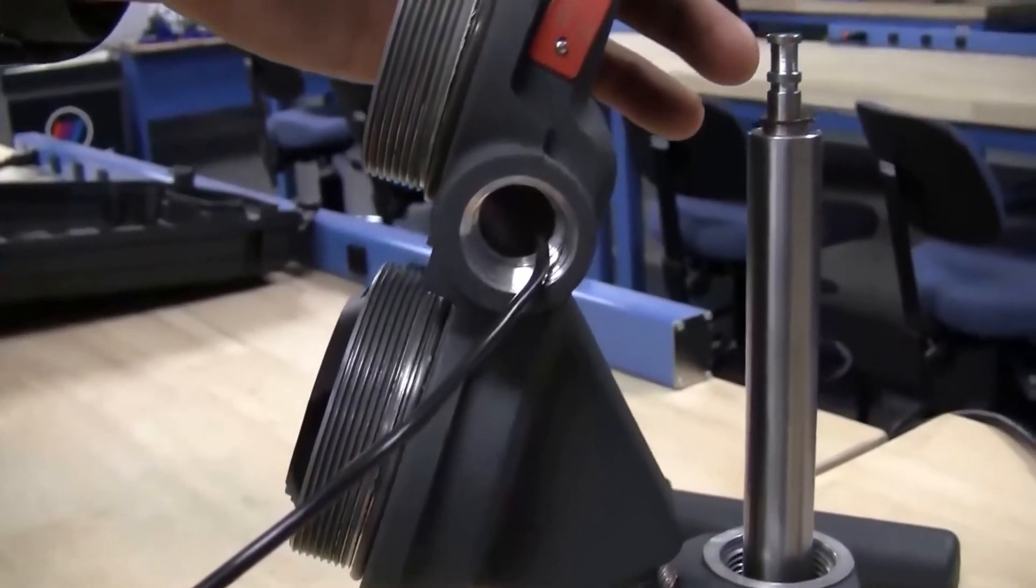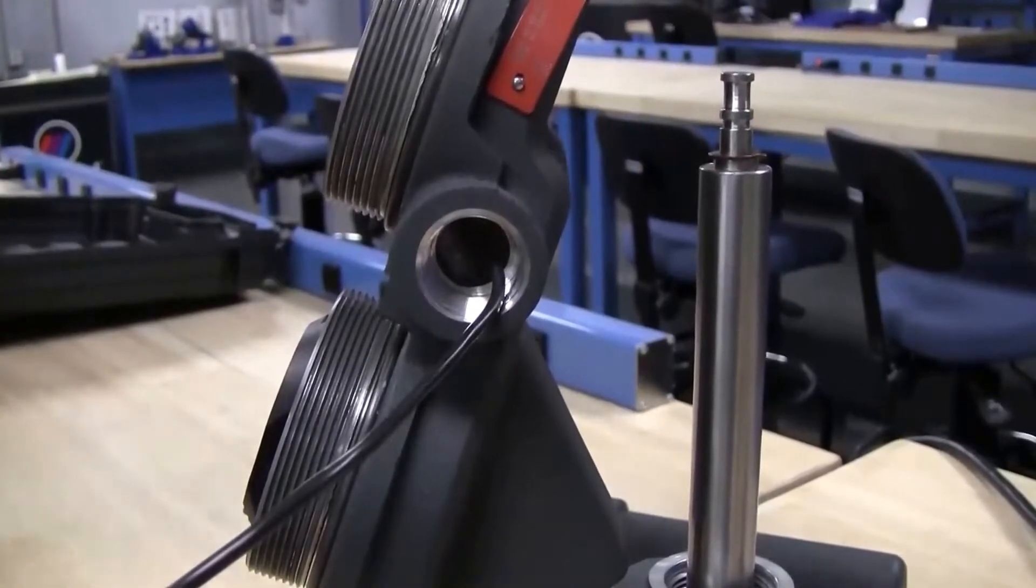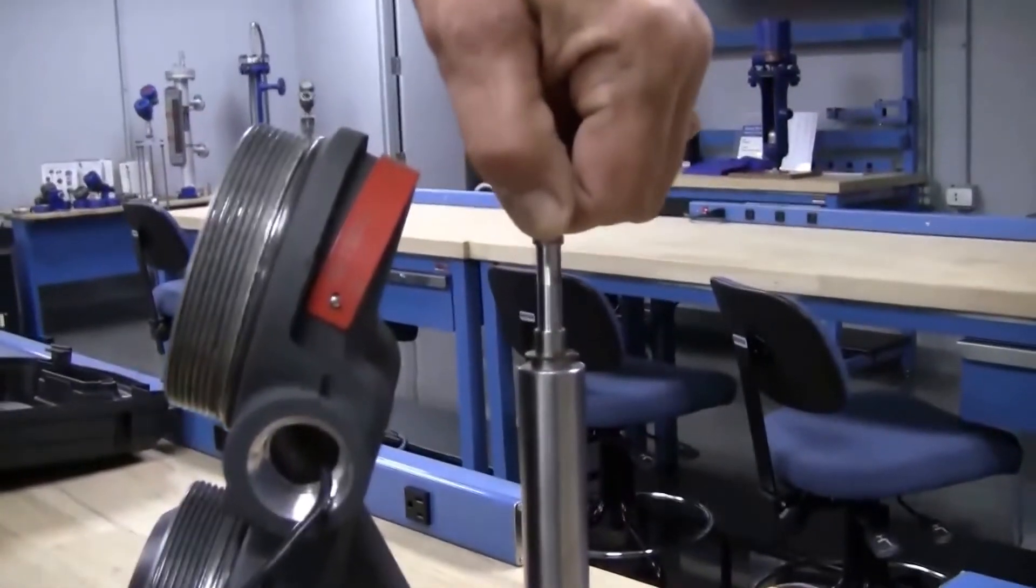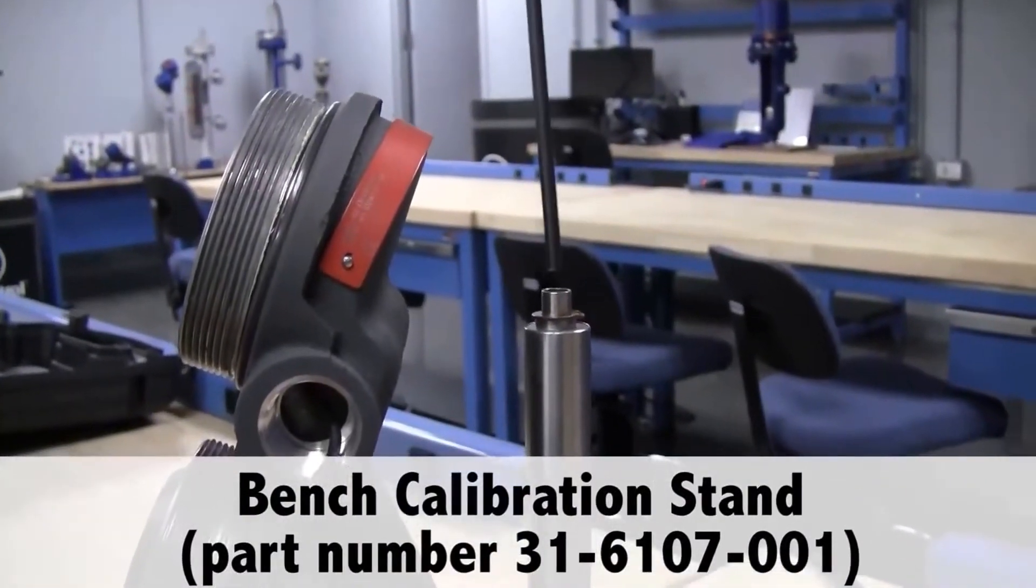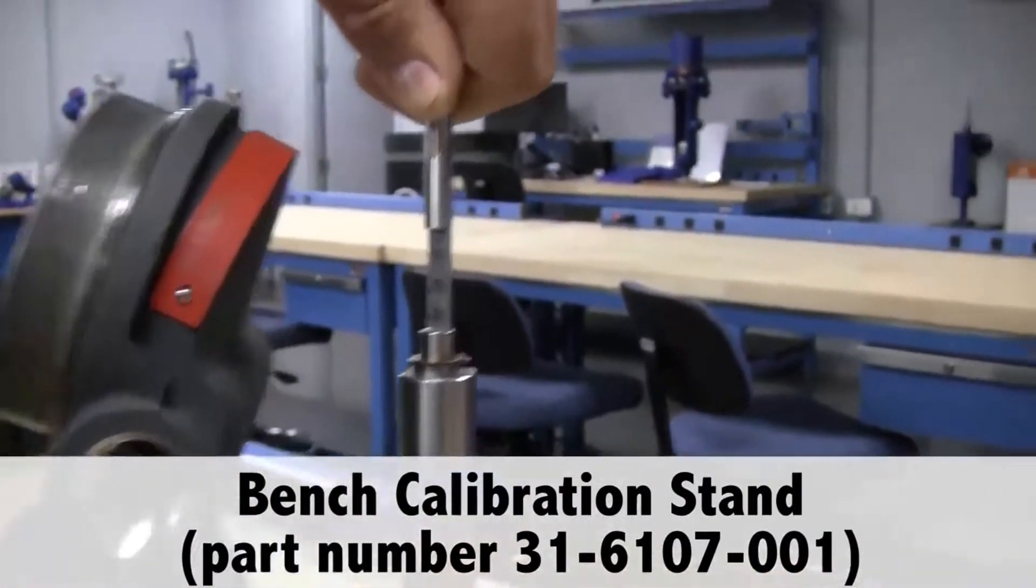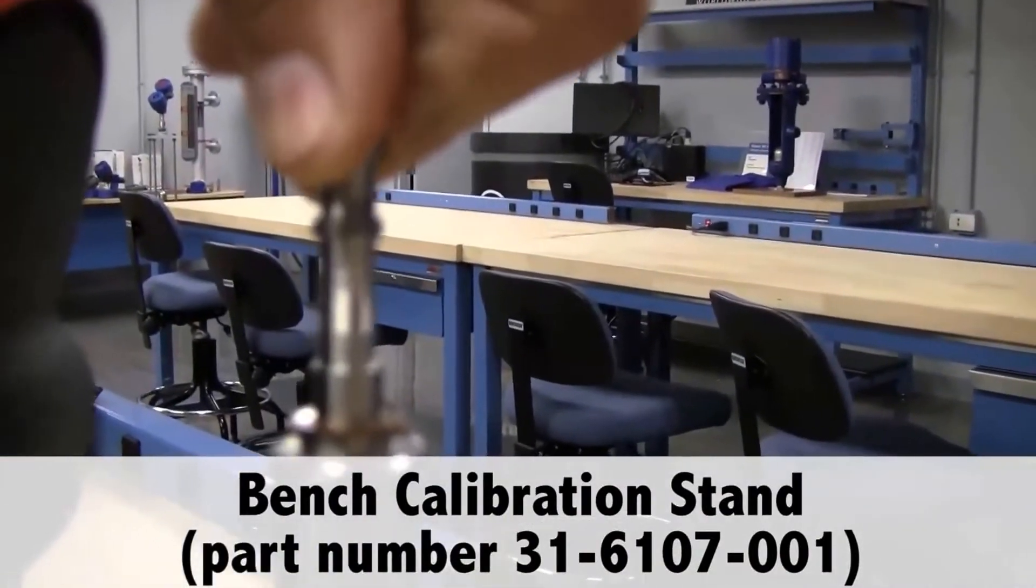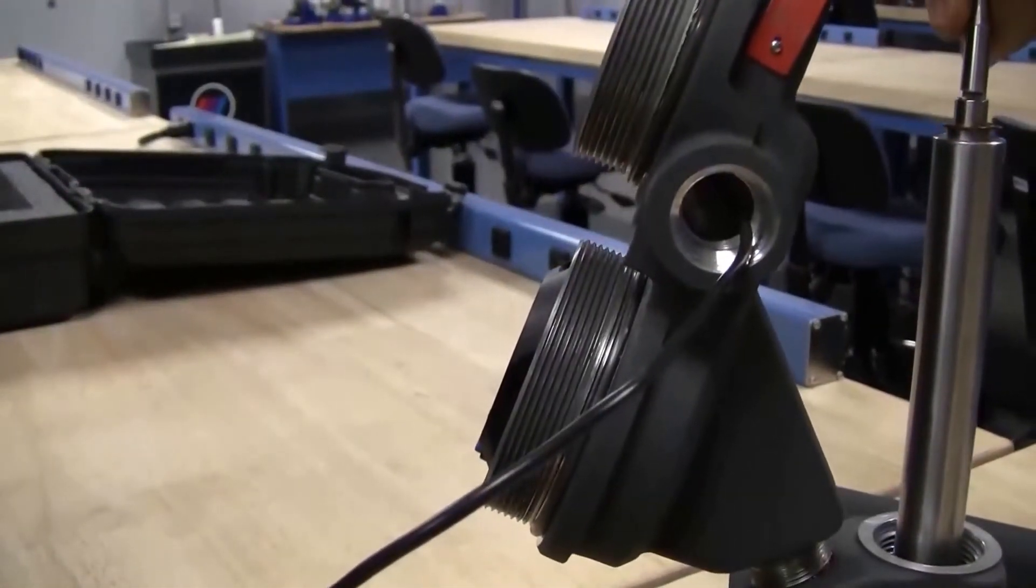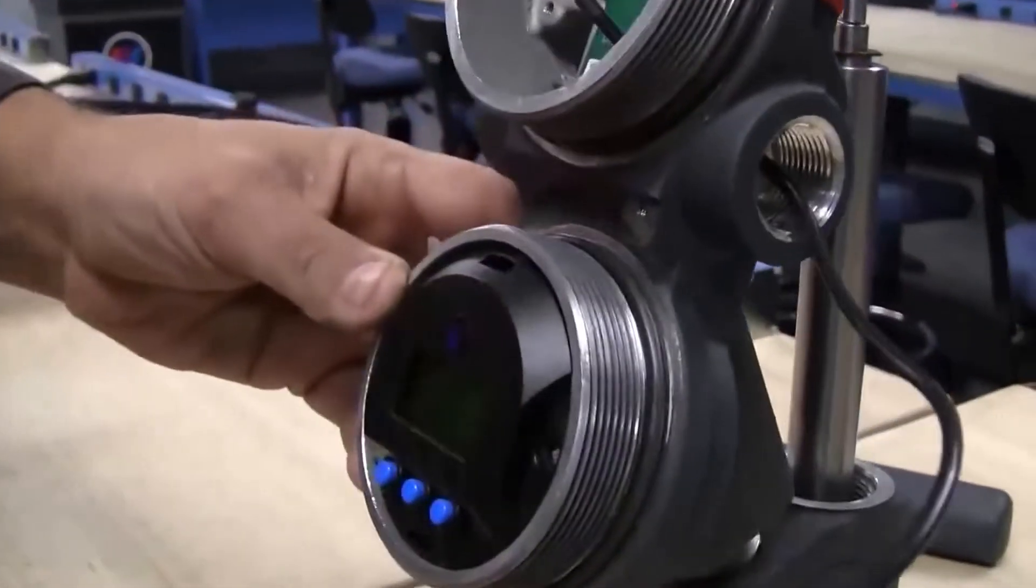You'll need to move levels if possible, and if you can get to two different levels, that would be good. We're going to simulate level movement on our test stand here with this LVDT core that we can move up and down. You can purchase this test stand if you wanted to use this, but if you can move levels, that would also work. So I'm going to start with the simulation of the level at zero or an empty tank, and then we'll go through the procedure here.